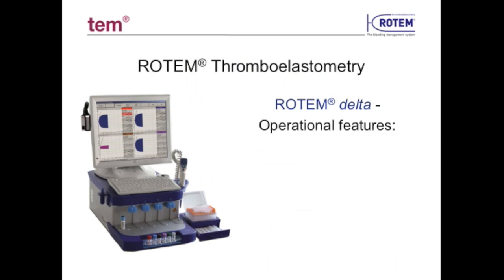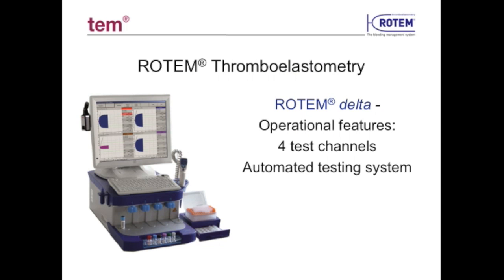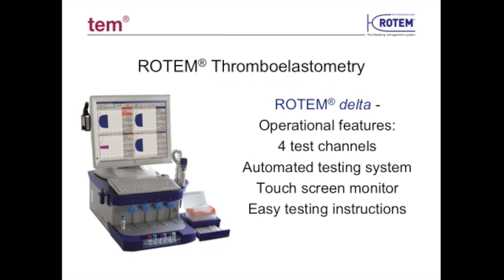The technology used in Rotem testing is done on a precision instrument called the Rotem Delta. This Delta allows for testing of four samples at a time, is relatively automated, has simple and intuitive touchscreen operation, provides easy-to-understand graphic and written instructions with each test, allows for weekly liquid quality control, and has a convenient barcode scanner. The Rotem Delta is a self-contained system that is easy to operate and maintain regulatory compliance for 24-7 readiness.